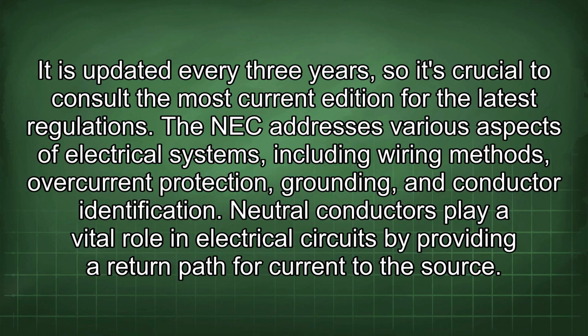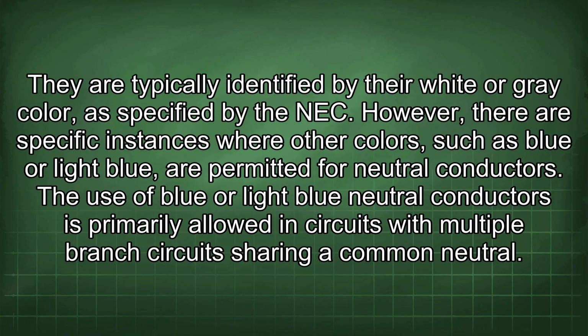Neutral conductors play a vital role in electrical circuits by providing a return path for current to the source. They are typically identified by their white or gray color, as specified by the NEC. However, there are specific instances where other colors, such as blue or light blue, are permitted for neutral conductors.